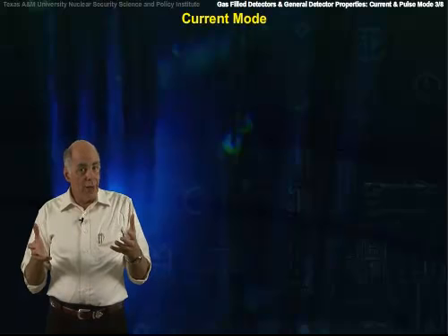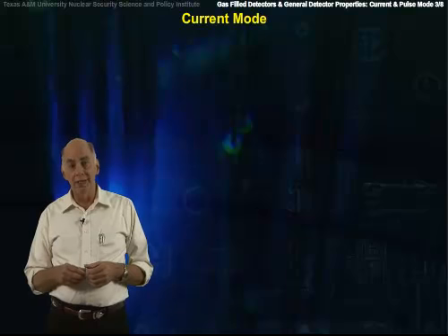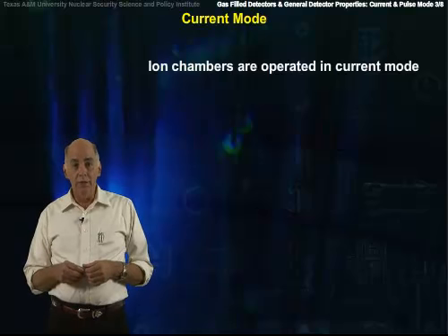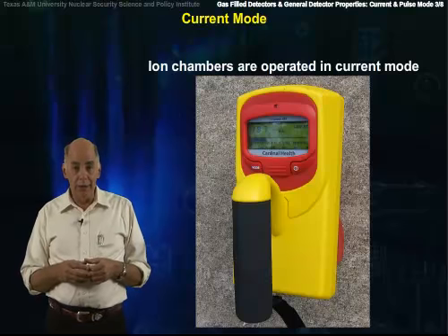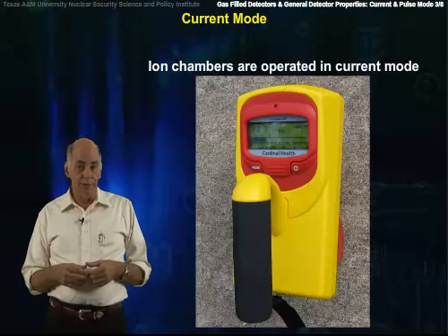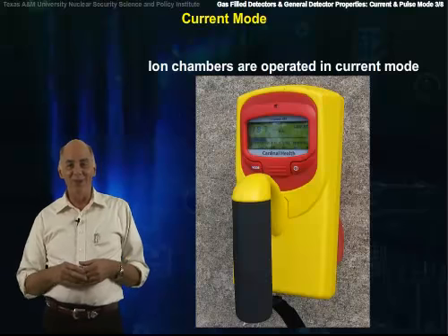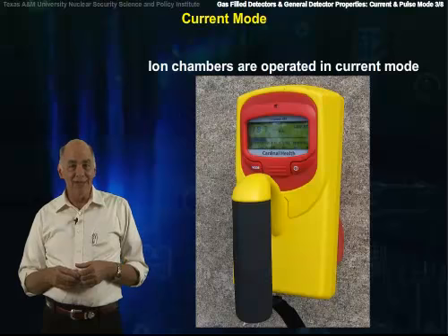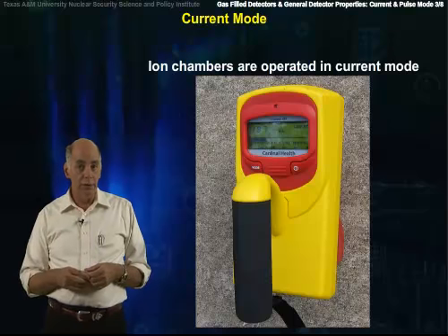Once you've got the charge separated, there are two ways to monitor the signal coming from the detector. One thing we can do is just measure the current itself produced by the ionization of the gas by the radiation. This strategy is used in ion chambers. The instruments that health physicists wave around in front of them when they measure dose is a gas-filled detector, and the current from the sensitive volume can be related fairly easily to dose.